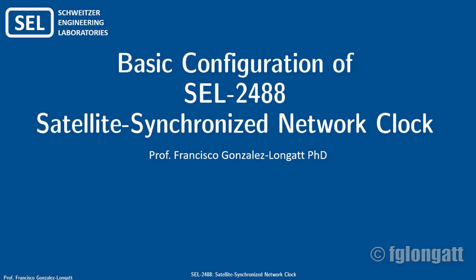In this case we use an Ethernet cable and the Ethernet port F of the SEL 2488, and we connect the computer using a laptop, and in this laptop I use the web browser and I establish the communication, define the administrator account, then I modify the IP address, and also I change the time zone of this device. In this case I include the data for Norway, my actual location at the moment.